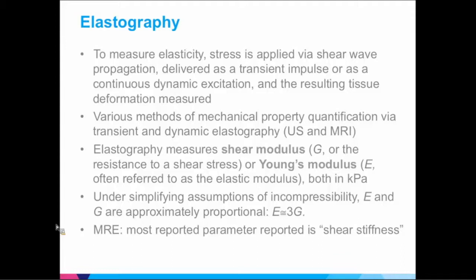With elastography you really have to apply stress on the organ of interest, in this case the liver. You can use shear wave propagation physically either as a transient impulse — that would be transient elastography — or you can do continuous dynamic excitation with ARFI ultrasound methods or with MRI. The resulting tissue deformation gives you the mechanical property of the tissue. There's sometimes confusion when reading articles: Young's modulus is applied typically to ultrasound elastography — Fibroscan is called E or elastic modulus, measured in kilopascals — while shear modulus G is mostly used for MR elastography, and there's typically a factor of three between the two.